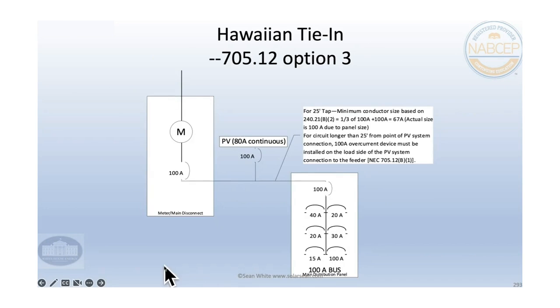So in Hawaii, electricity is really expensive, and they have the greatest penetration of solar in the country per capita. And so a lot of times they have these all-in-one meter mains like this. And so here we're connecting to a feeder. We're showing if this is less than 25 feet, they don't need to do anything special when they're connecting there. They're showing 80 amps of continuous inverter current with a 100 amp bus bar. So that's kind of a neat thing to do there. They give you as much as you want.